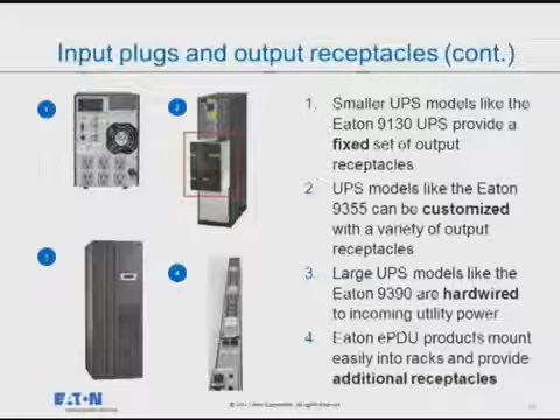I'm building a large system. I've designed it for 18 kVA. Last thing I want is somebody to arrive on a floor and start saying, oh, hey, look, I want to plug in my drill, or I want to plug in a vacuum cleaner into that, right? It happens. It sounds stupid, but it is so critical. And when I hear people talk about downtime and what happened, well, you wouldn't believe it. Is probably typically how the story starts. It happens. These give us the ability now to control and turn off receptacles as we need to.